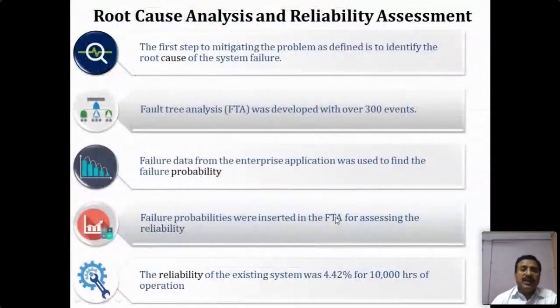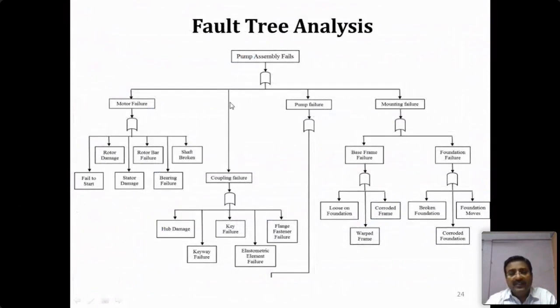So root cause analysis and the reliability assessment is to be done. The reliability of the existing system was found to be 4.42% for 10,000 hours of operation. So fault tree analysis was developed for 300 events. So this is the complete analysis given in our research article. So pump assembly failed due to various reasons. One of the important reasons is motor failure, another coupling failure, then pump failure, and the mounting failure. So why does the motor fail? Fail to start, rotor damage, stator damage, rotor bar failure, bearing failure, and the shaft broken. These are the different possibilities for the motor failure.